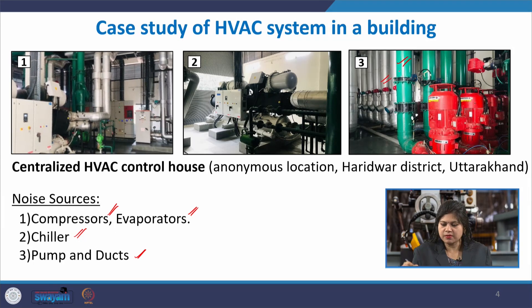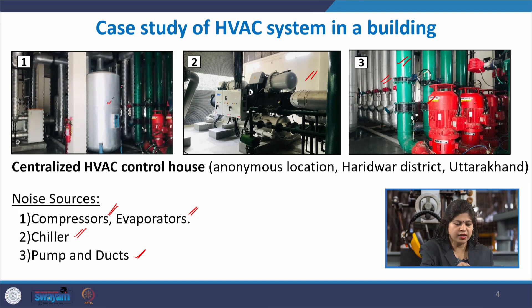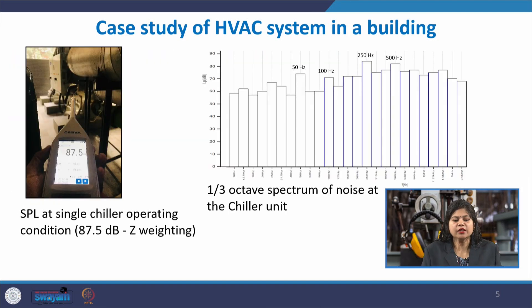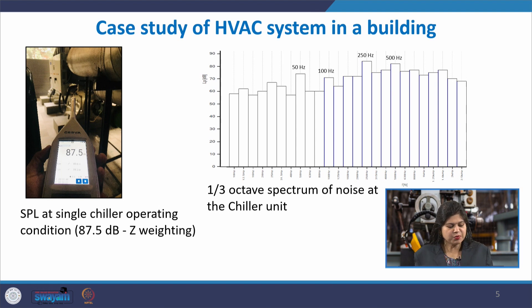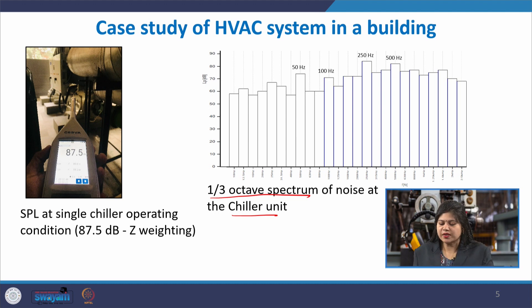When we went into that HVAC system and measured the noise level, one typical measurement at a single chiller operating condition showed an SPL of 87.5 decibels on the Z-weighting scale. The one-third octave spectrum shows the noise is typically low-frequency content, with major peaks at 50 Hz, 100 Hz, 250 Hz, and 500 Hz.